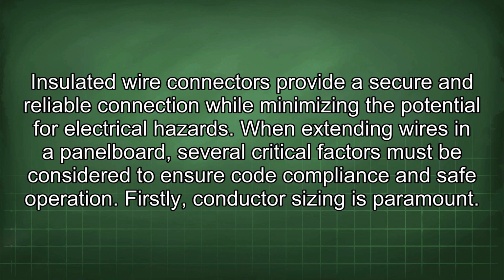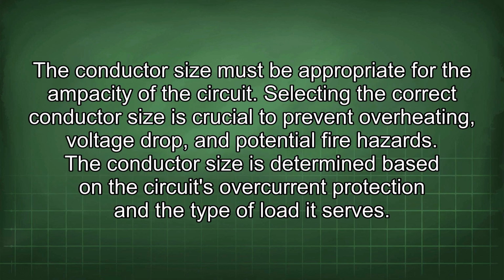Firstly, conductor sizing is paramount. The conductor size must be appropriate for the ampacity of the circuit. Selecting the correct conductor size is crucial to prevent overheating, voltage drop, and potential fire hazards. The conductor size is determined based on the circuit's overcurrent protection and the type of load it serves.